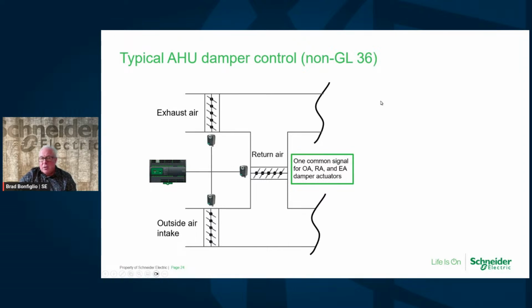So let's talk about air handler control. When we're looking at it, this is a traditional, non-Guideline 36 approach. It was very common in the past, especially in low bid situations, to have an actuator on each damper for outside air, return air, and exhaust, but only one output going to those. There was nothing that specified you had to have independent outputs for these. One is doing the same signal to the others. Typically, you do this in low bid situations where you have one output because you're saving on the cost of upgrading a controller. There are a lot of reasons why you would do it this way.